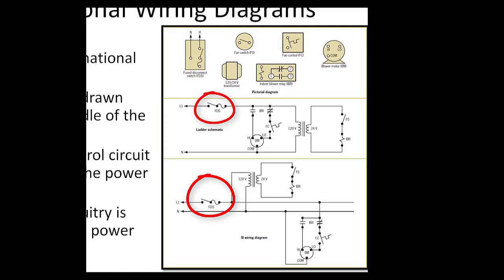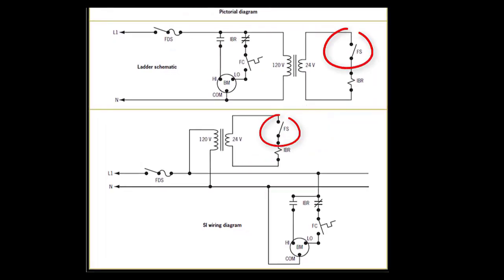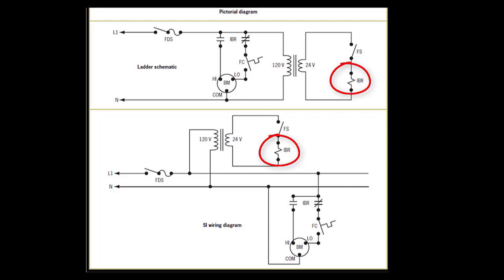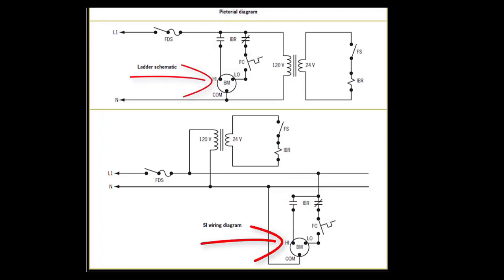When L1 disconnect is closed, the transformer is powered. When FS is closed, the IBR coil is energized. At this point, the normally closed contacts open, and the normally open contacts close. The BM runs at high speed.